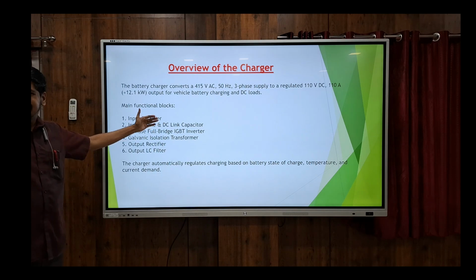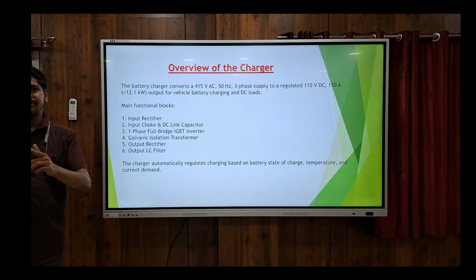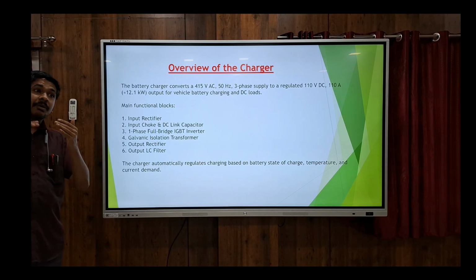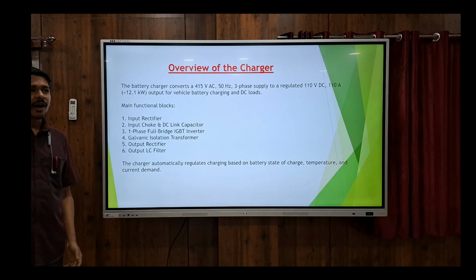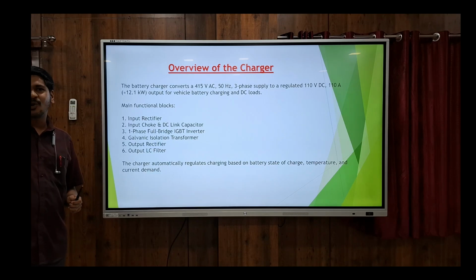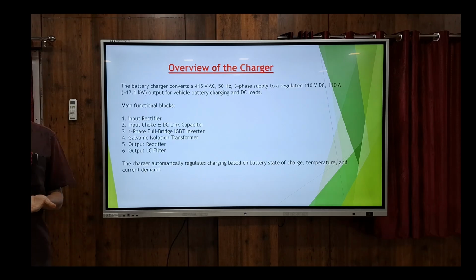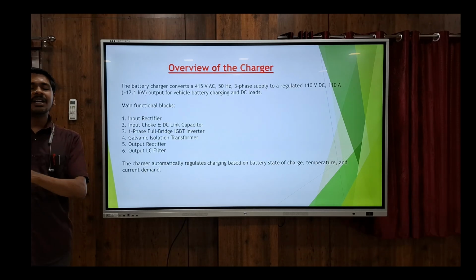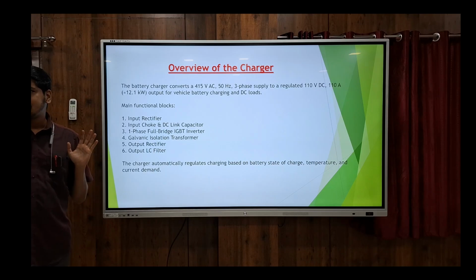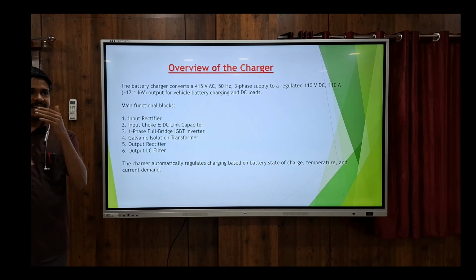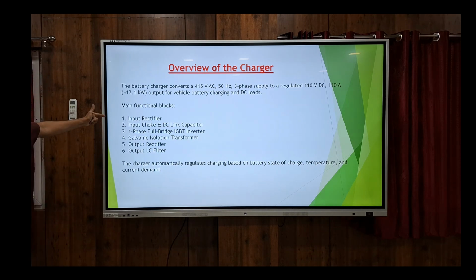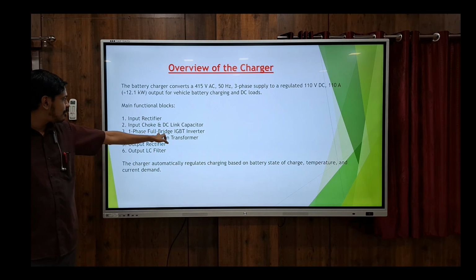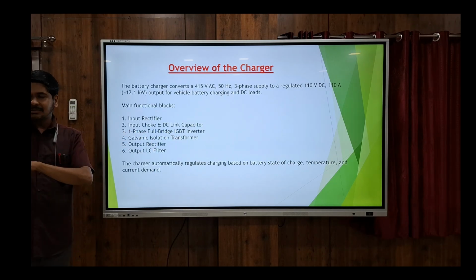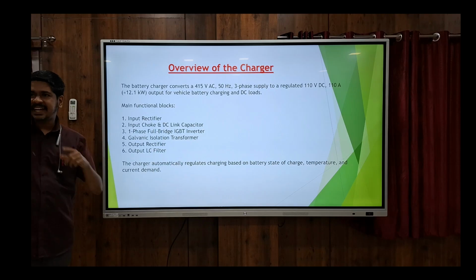Then the output generated by the initial stage rectifier will have a voltage much higher than our requirement of 110 volt. Because 415 volt, if rectified, will give a value of 415 into root 2 times, it will be nearly 600 plus volts. But for charging the battery we need 110 volt only. So we need a DC to DC conversion stage. For that the next stage is the single phase full bridge IGBT inverter. It will convert this DC into high frequency AC.